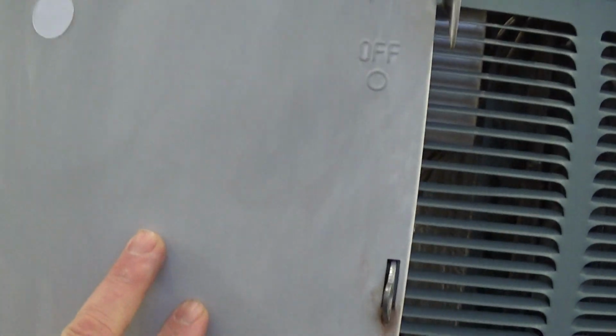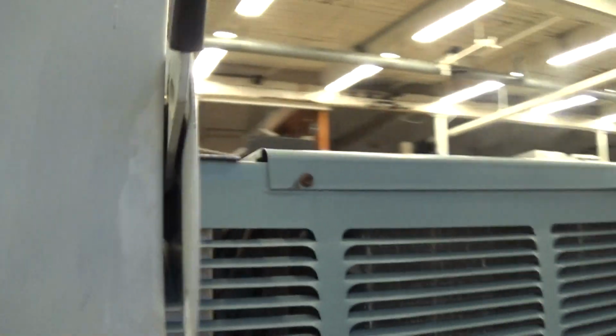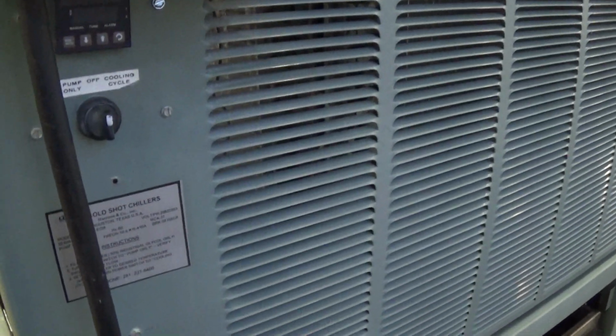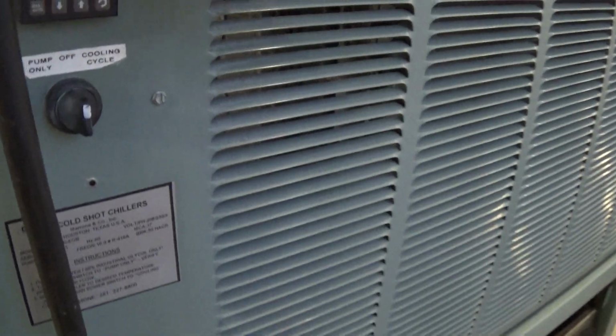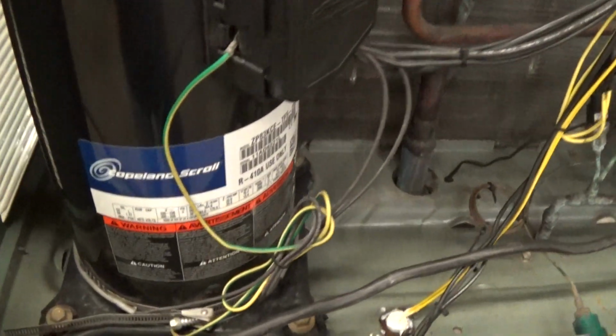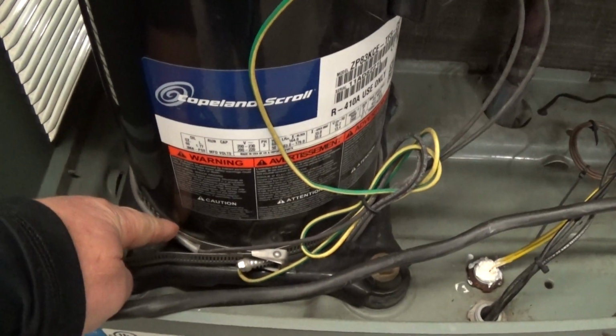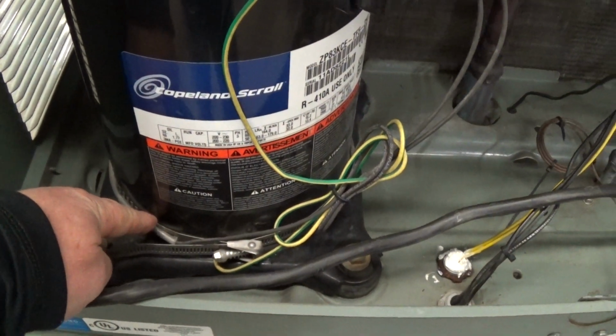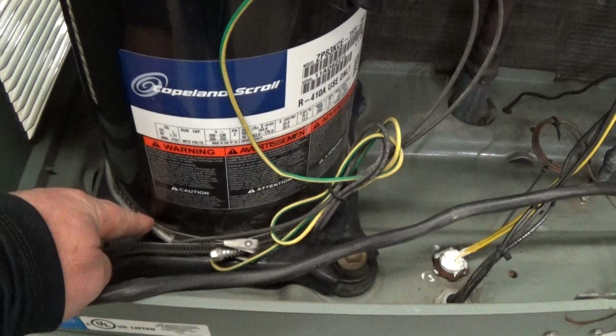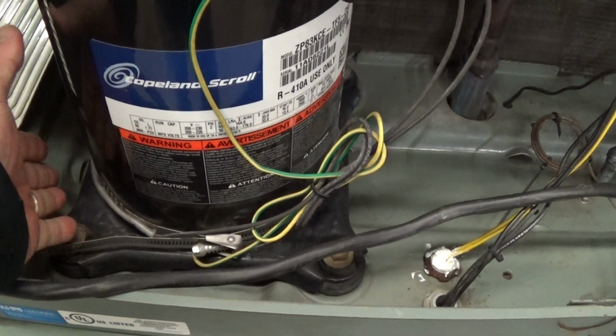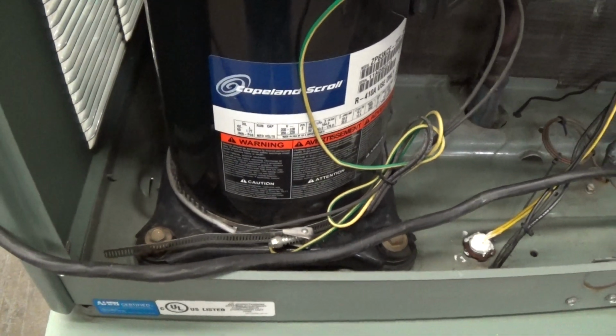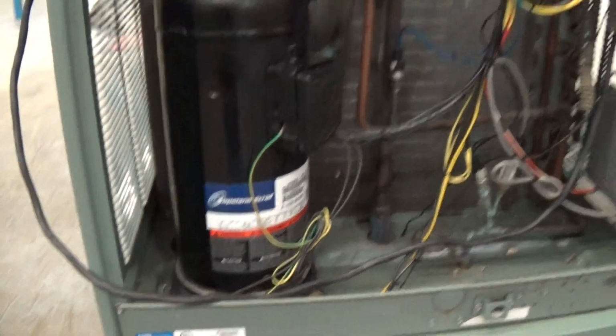We're going to ship it with the disconnect. Don't turn it off at the disconnect unless it's going to be for a long time, because even in this state right here, where the power is off here, the power is still live coming into the chiller, and also keeps the heater on this crankcase heater here. So when you first get this chiller, we want to make sure that this heater here, which is hot to the touch, is on for at least 12 hours before you actually run the chiller.